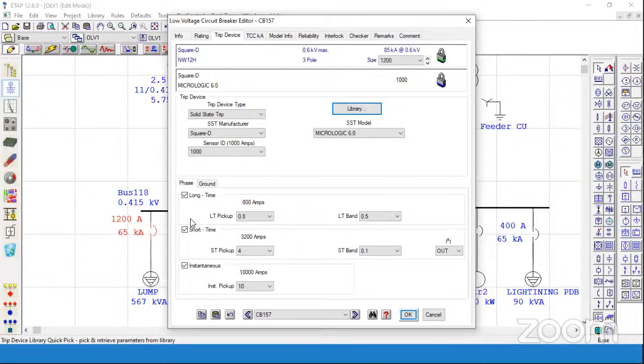Then the short circuit time. The short circuit time depends on the short circuit current. Normally the fault current will go up to 10 to 12 times the full load ampere. In order to protect the equipment, we set these parameters to four times the full load current, that is 4 into full load ampere. And as there is no downstream network here, we will adopt the minimum time delay, that is 100 milliseconds. This is the instantaneous protection, that is within 0 milliseconds. If any fault current goes beyond a certain value, then it should operate within 0 milliseconds. So we will take this protection in line.